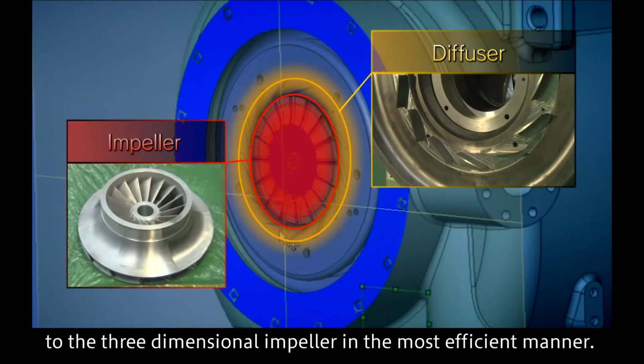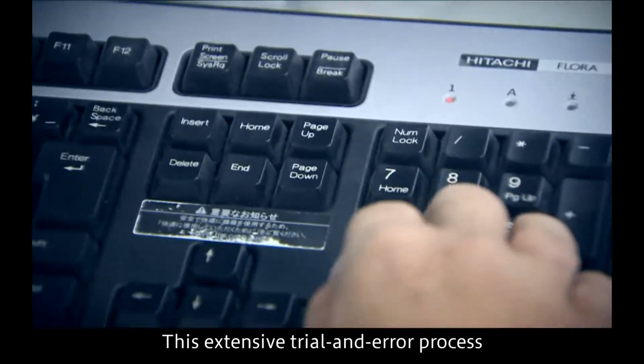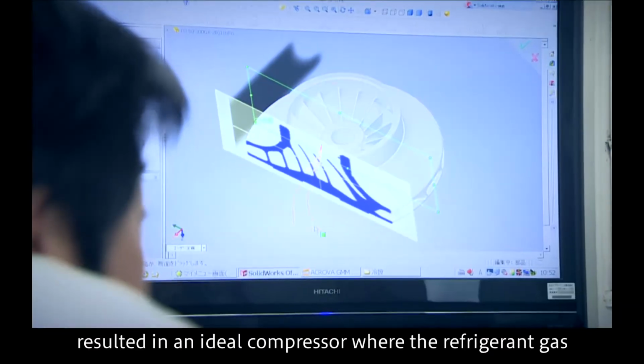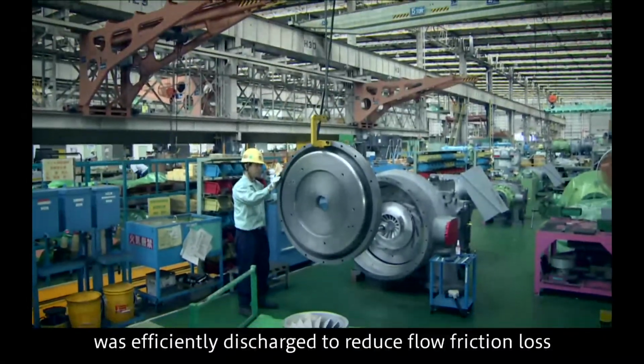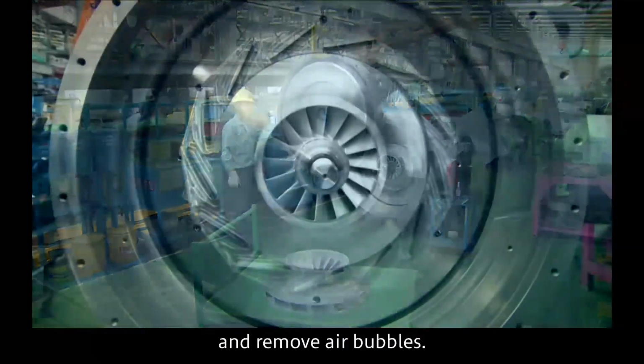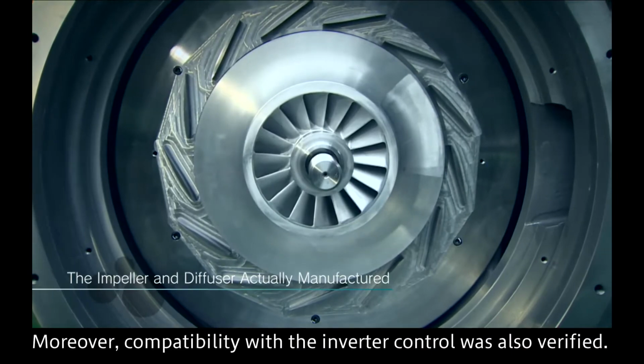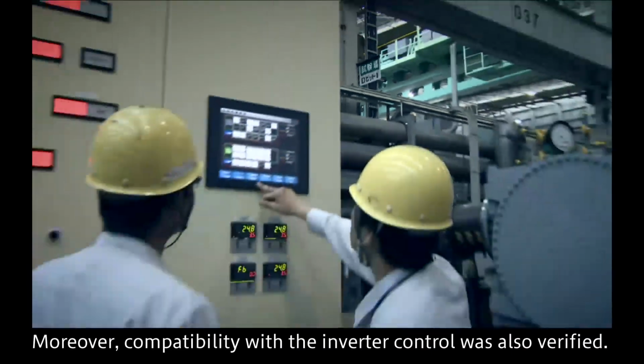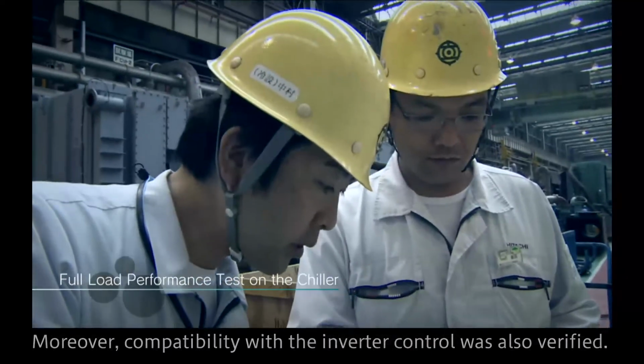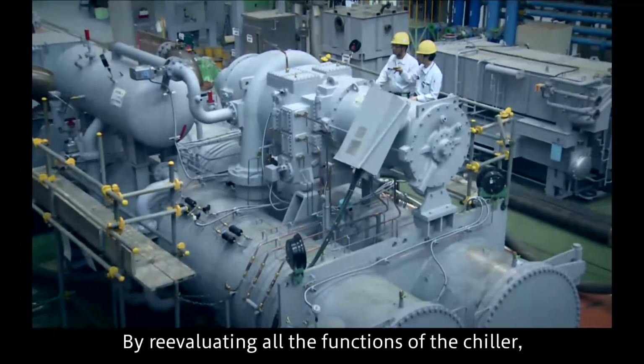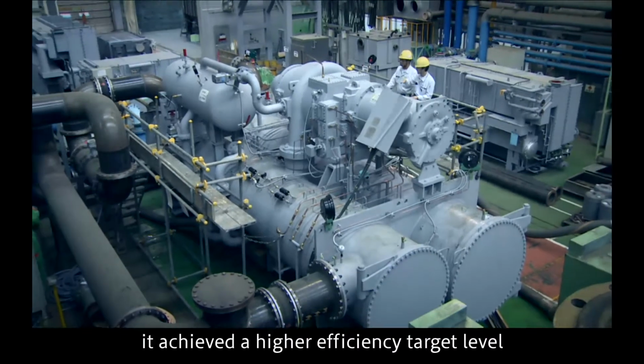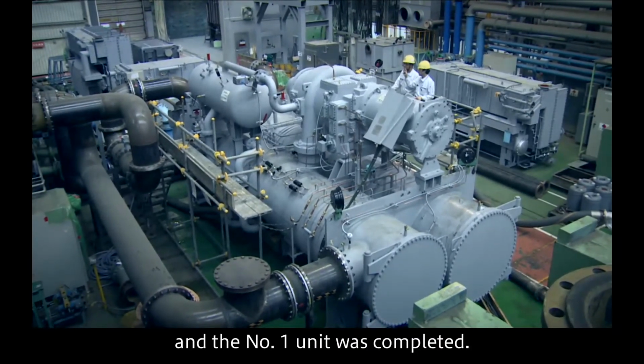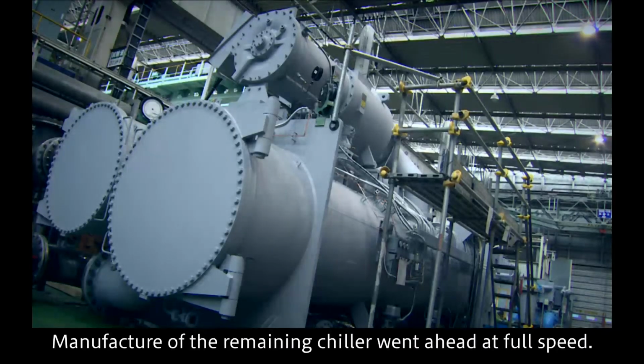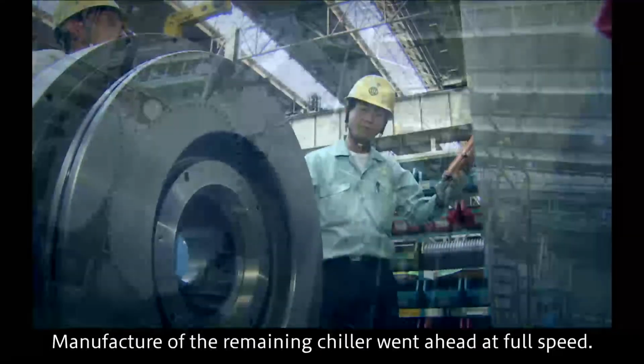to the three-dimensional impeller in the most efficient manner. This extensive trial and error process resulted in an ideal compressor where the refrigerant gas was efficiently discharged to reduce flow friction loss and remove air bubbles. Moreover, compatibility with the inverter control was also verified. By re-evaluating all the functions of the chiller, it achieved a higher efficiency target level and the number one unit was completed. Manufacture of the remaining chiller went ahead at full speed.